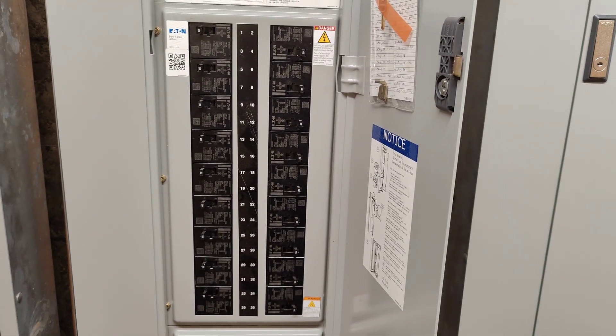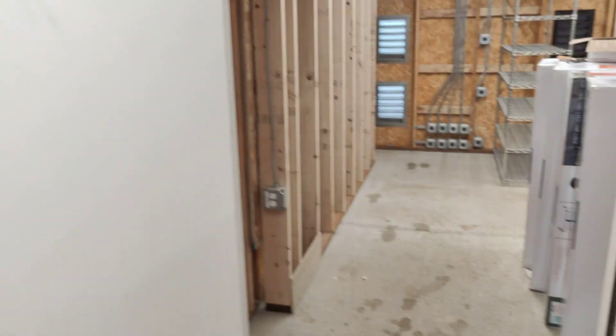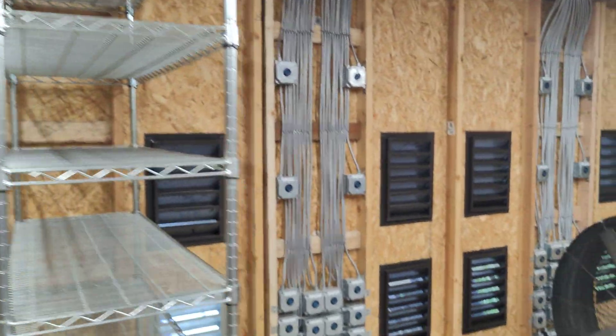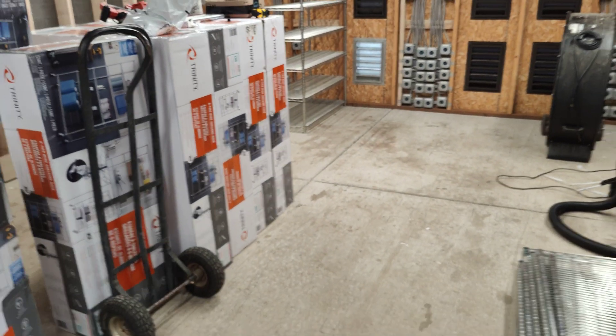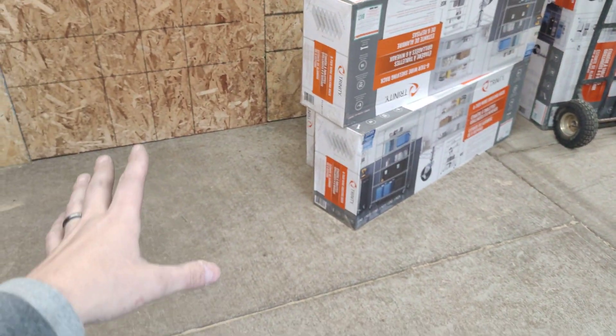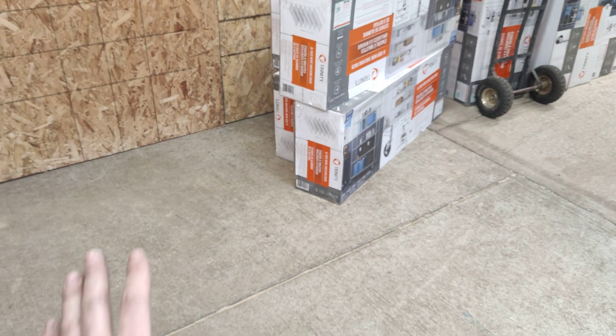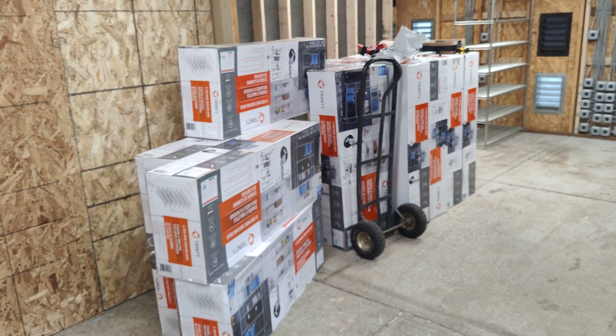The most important thing is the transformer. So the transformer is 300 kVA — that's 300,000 watts running all these rigs. Now how many rigs is that going to be? There's going to be 60 racks in this room, four rigs a rack. And then over here it's going to have, I think, 7 more racks at 4 rigs — if I remember correctly. So at the end, that would max out that 300 kVA.